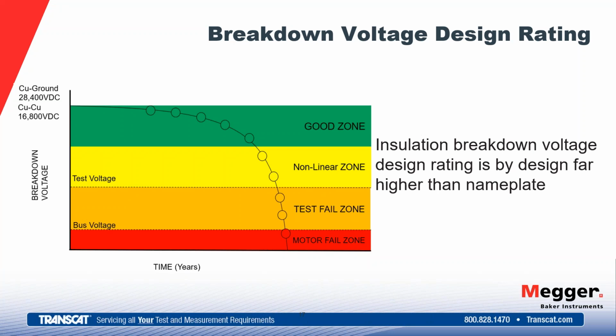The only way the insulation will be degraded is by excessive charge flowing through the weakened material, and that's not happening with a good insulation system. However, if your insulation is degraded, then the current that flows with the arc can potentially cause further carbonization of that degraded area. Since the test is well controlled and regulated, as in that slide we talked about, vintage instruments, this instrument in newer modern times has the ability to stop the test before that occurs. So it minimizes any potential carbonization of that motor.